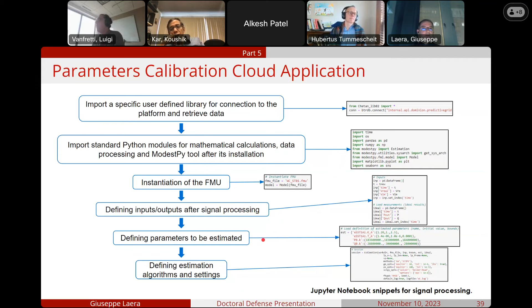The calibration was carried out considering 4 parameters for this case and 2 scenarios: ambient and transient conditions. From the results, the exciter gain Ka keeps a value of the same order of magnitude in both scenarios, whereas the time constant Ta has a difference of several orders of magnitude.